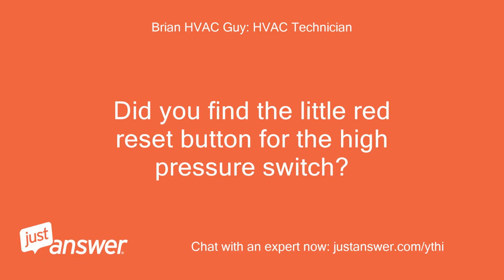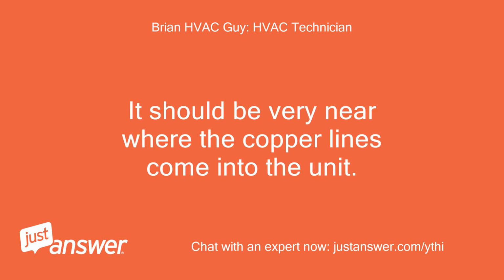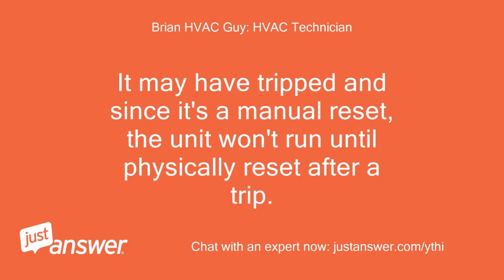Did you find the little red reset button for the high pressure switch? It should be very near where the copper lines come into the unit. It may have tripped, and since it's a manual reset, the unit won't run until physically reset after a trip.